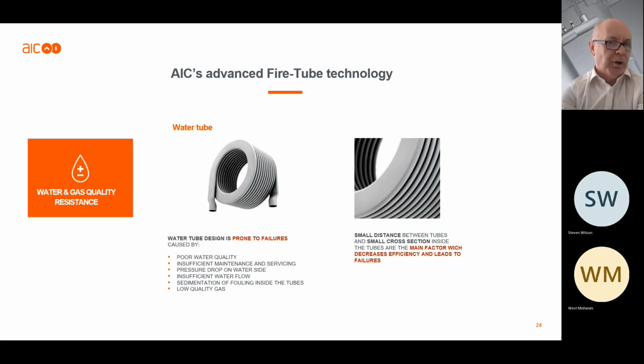Okay, so if we look at a traditional water tube stainless steel heat exchanger there, you can see from that there's very narrow waterways. So if you've got any contaminants in the water, you're going to get them building up at the base of that heat exchanger. And when they build up there, it's very difficult to move them. So what that does is effectively create a hotspot, which will affect the efficiency of the heat exchanger and ultimately will lead to premature failure. And the same when you look at the flueways in between the coils there, they're very narrow. So if you've got any build up, poor gas quality, you'll have build up of gas residue there. You'll get some calcification in between the fins, and the same result: it will affect efficiency and lead to premature failure.